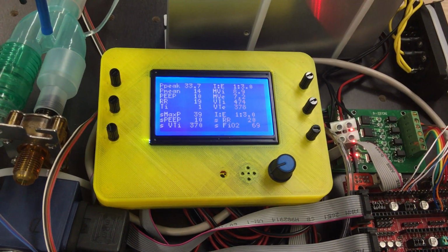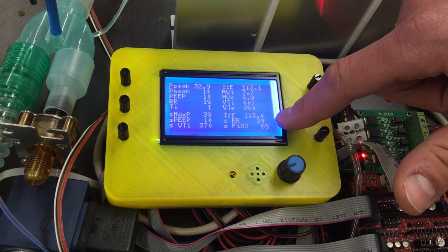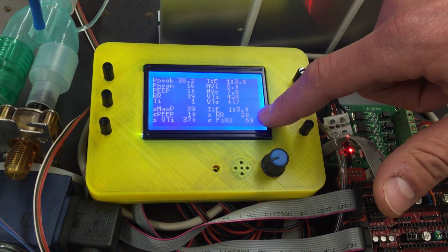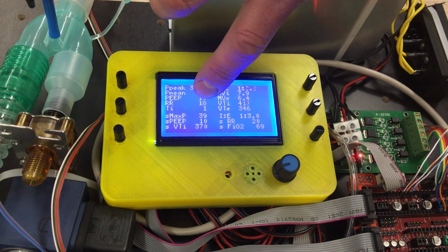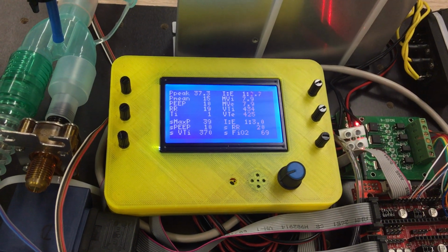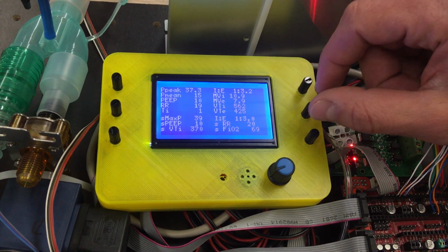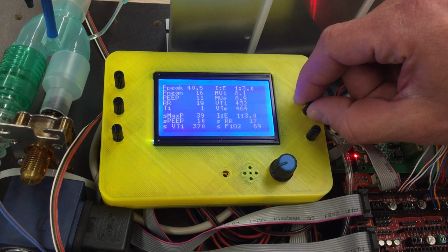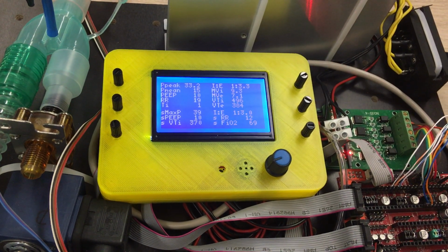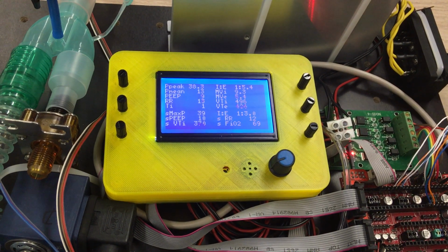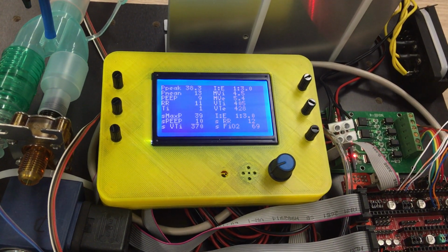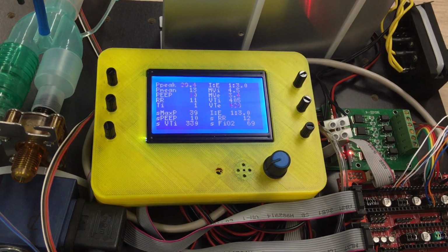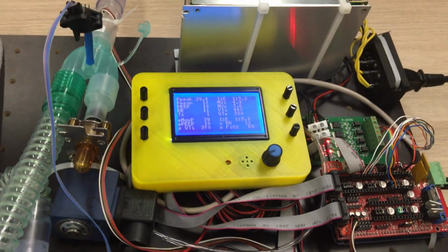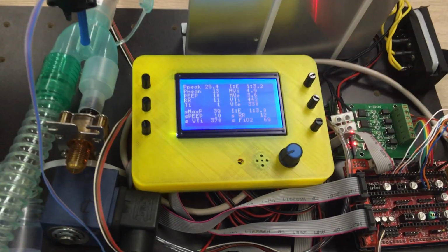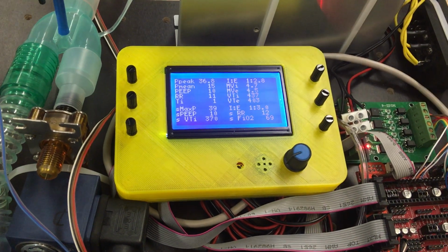So now we can see there is a respiration rate of 20 breaths per minute. And the actual respiration rate is here. So you can see it is close to the set value. So let's try setting respiration rate to 12, and we will see what happens. We can hear that the breathing process has slowed down, and also probably the values of minute ventilation will be lower.